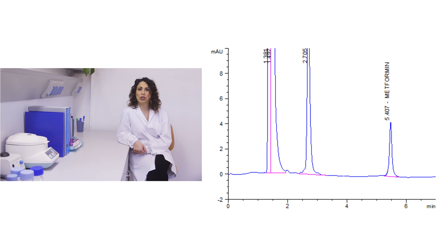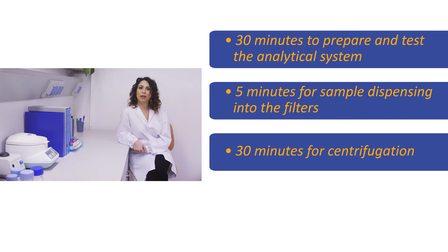The time we took for this analysis is as follows: 30 minutes to prepare the test and the analytical system, 5 minutes for the sample dispensing into the filters, 30 minutes for centrifugation, about 70 minutes to analyze all the samples. In these conditions, you are able to report by 12 o'clock each day and use your instrument and your work to perform other analysis. Currently, the Eureka kit I have presented to you is an Eureka exclusive, available for metformin dosing in HPLC. Let's summarize.